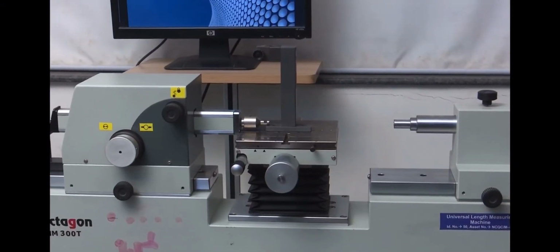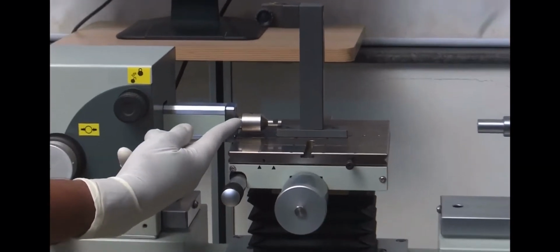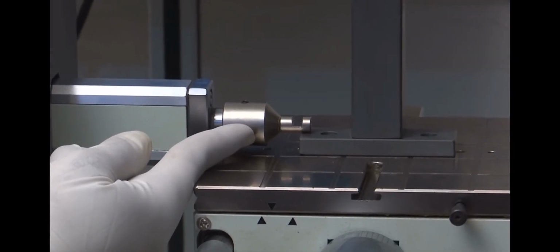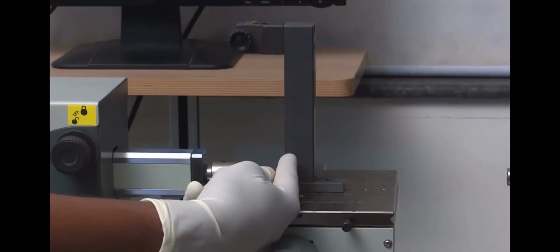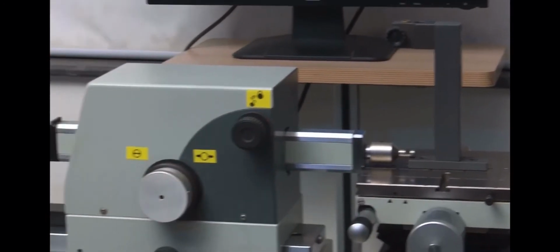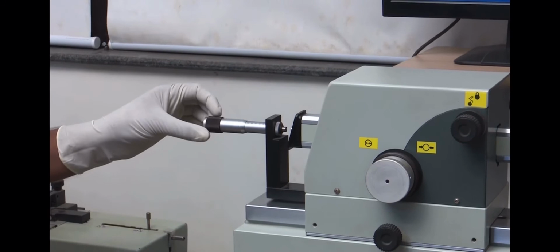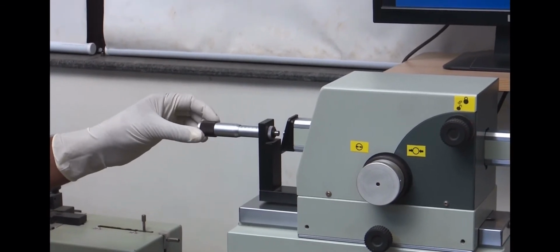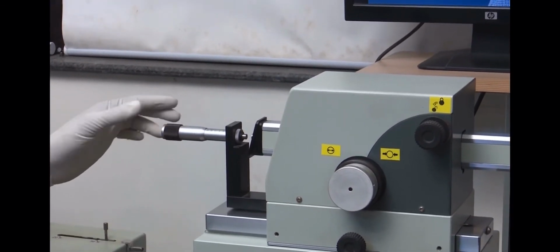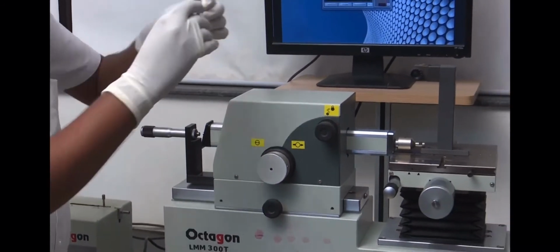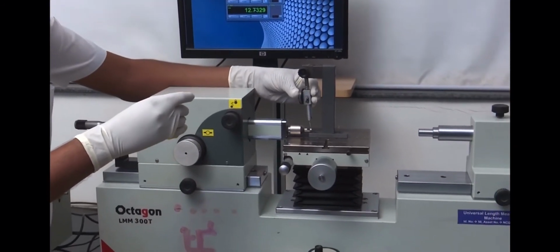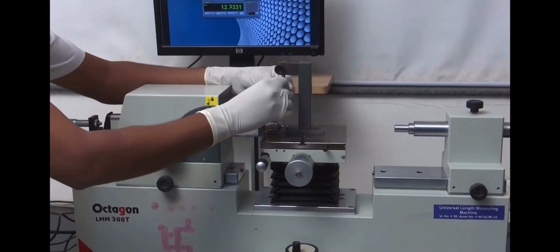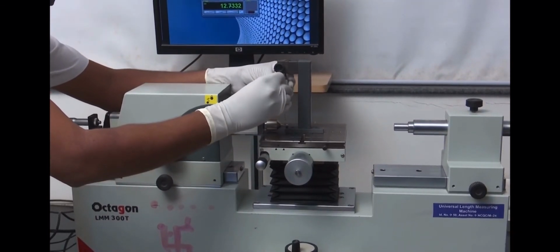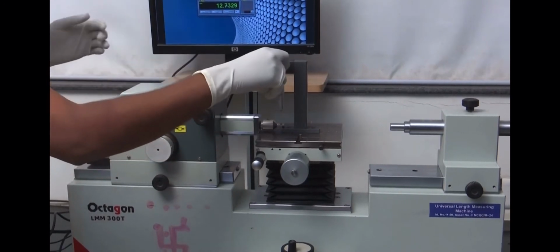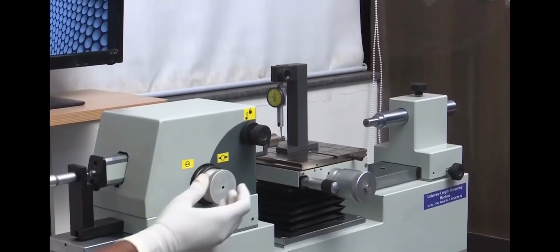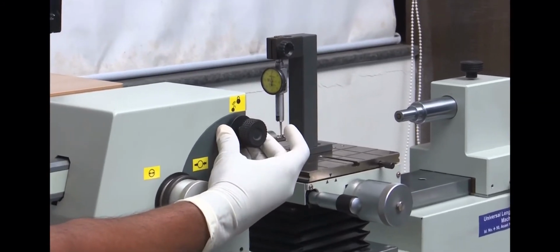All accessories are fixed. I have already clamped lever dial calibration anvil on measuring axis, dial holding fixture on machine table, driving unit on backside of measuring axis. And now I am holding lever dial in the holding fixture. Here the measuring axis is locked in fine adjustment mode.